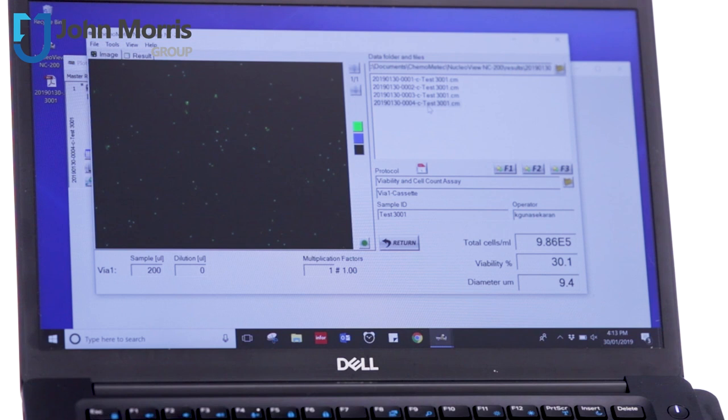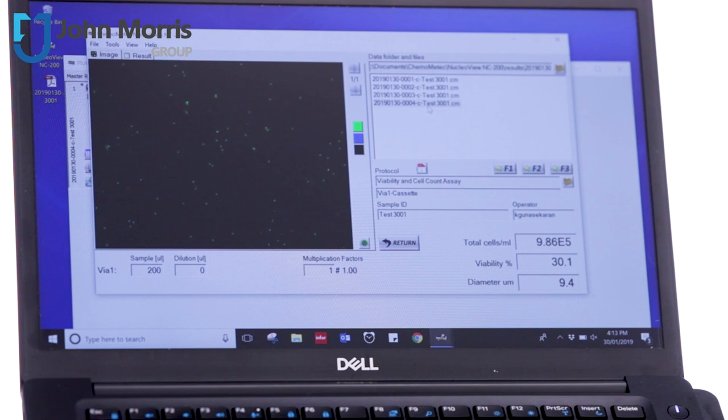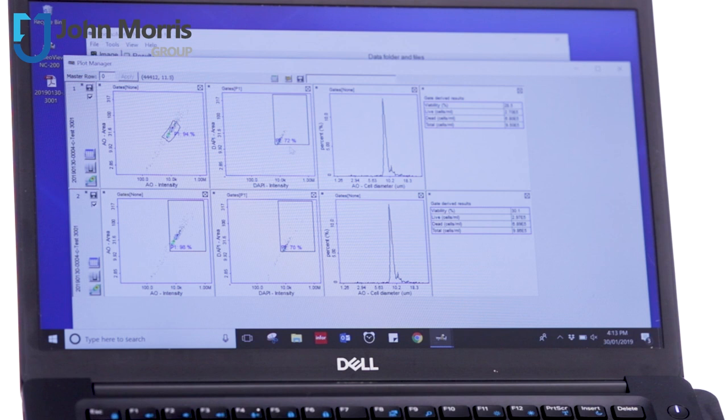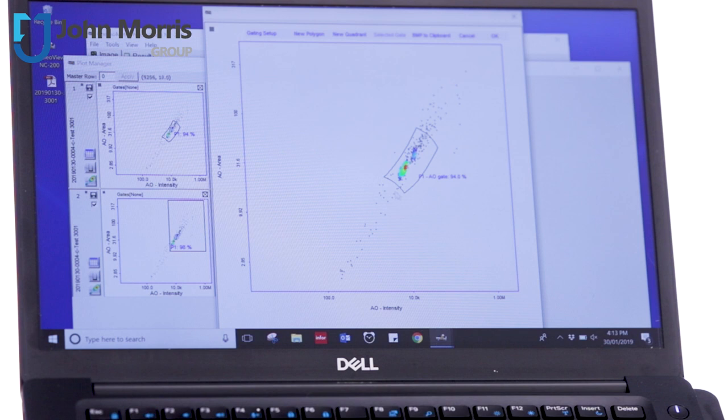Another really sweet feature of this instrument is you can right click on any of your test results here and you can go to the raw data and you can actually change your gates. Now you can see this is what it would usually look like. And here, if I double click on this, I've actually narrowed the gate to a defined area.